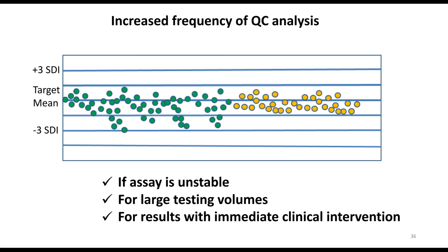QC should also be analyzed more frequently if the results are acted upon immediately with a clinical intervention. In this case, we would want to discover an error quickly so that physicians can potentially be notified before an incorrect intervention occurs.